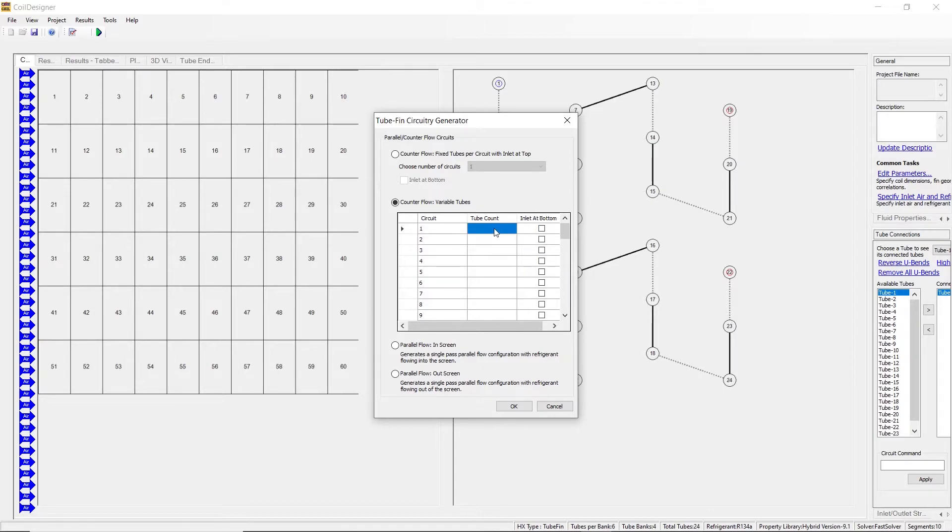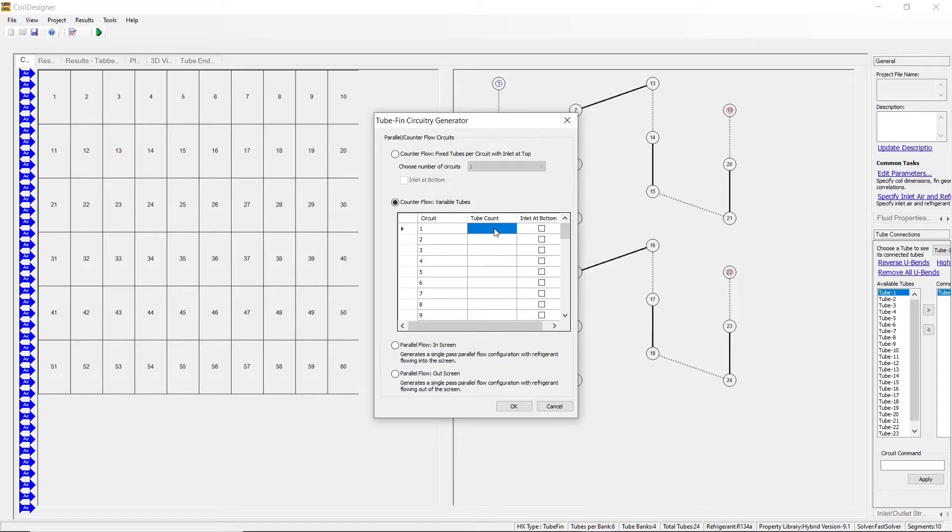Here you are not given an explicit number of circuits to limit you. However, the number of tubes you enter in the tube count column as a whole may not exceed the number of tubes per tube bank that you inputted in the coil designer wizard. In our case, we inputted six.